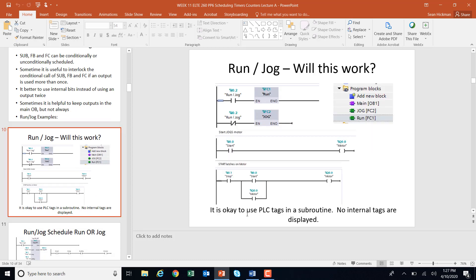Let's look at this run/jog example. We have two functions — one is run, one is jog — and they're conditionally scheduled depending on whether the run/jog button is made. It looks like it's the same button because one is programmed open and one closed, so it's either going to call run or jog. In jog mode the motor runs when the start button is pressed. If I switch to run mode — unschedule jog and schedule run — when I hit start I get memory, and the motor holds on. So inside these subroutines I've used global tags.